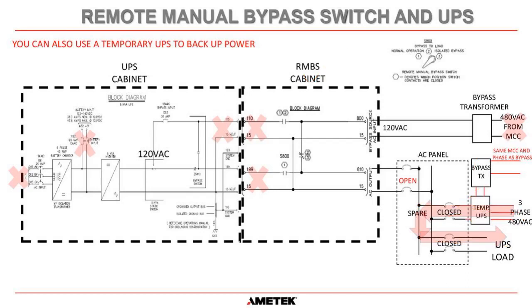So yes, you probably do have to pay extra to get a rental UPS from a UPS company to be able to do that. And obviously there's more wiring and more expense. But this is what I call the belts and suspenders way of doing it. This way you know that you can do the replacement without any issues whatsoever if you install a temporary UPS to backfeed the AC panel. The procedure is exactly the same, whichever way you do it, but it is a good way to install an RMBS while remaining on a UPS backup to your load circuits.